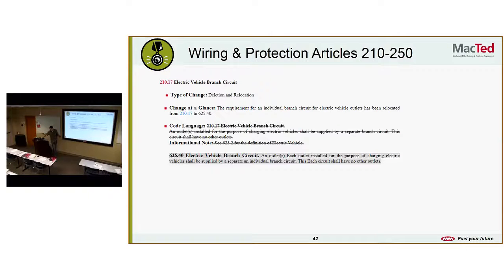Electric vehicle branch circuit. Oh, deletion and relocation. Throwing us a curveball here. New article. So they relocated the requirement for an individual branch circuit for electric vehicle outlets. They removed it from 210.17 and put it in 625.40. It says each outlet installed for the purpose of charging electric vehicles shall be supplied by a separate individual branch circuit. This circuit shall have no other outlets.